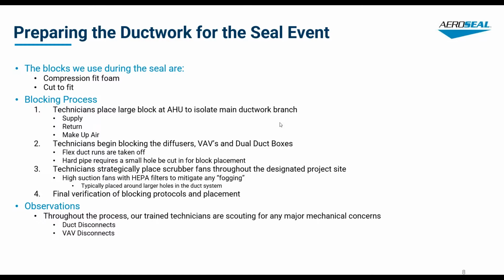Then technicians will begin to block off the diffusers, VAVs, and or dual duct boxes in the facility. In order to do that, we'll take off the flex runs and put the block there. If it's hard pipe, then we'll cut a small hole in the hard pipe and place the block in there. After the sealing process is over, obviously we would put it back together and patch the hole if we had to put a hole in it.